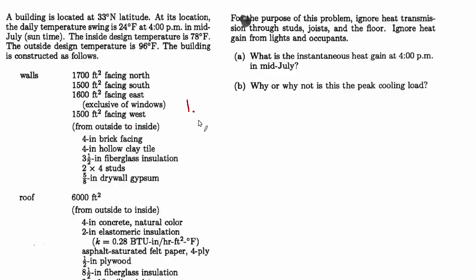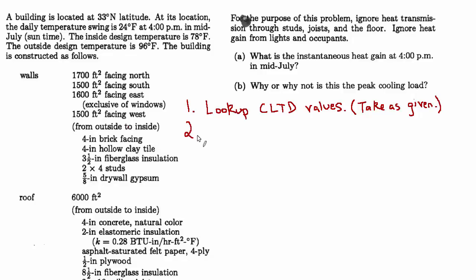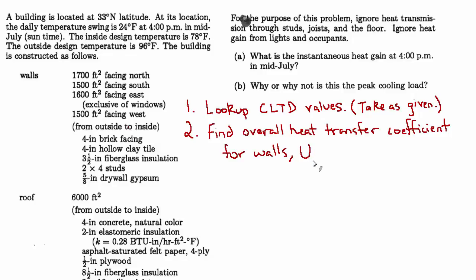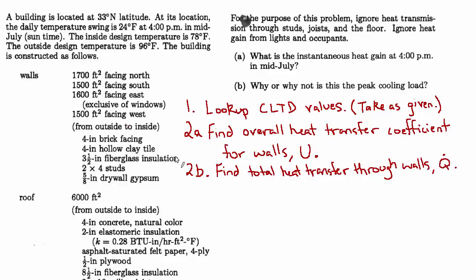The plan of attack: first, we look up the cooling load temperature difference values. On actual test problems they typically wouldn't require looking this up in the ASHRAE Fundamentals, so we'll take them as given. Next, we'll look at the walls, consider the materials, thicknesses, and resistance values, and figure out the overall heat transfer coefficient U for the walls — call this step 2a. Then in step 2b we find the total heat transfer through the walls, Q-dot for the walls. Similarly, in steps 3a and 3b we find U and Q-dot for the roof.